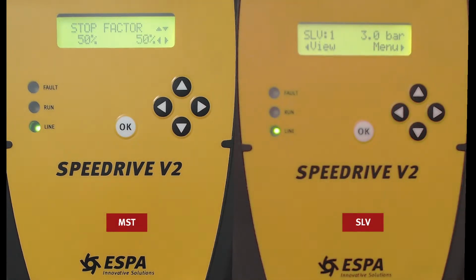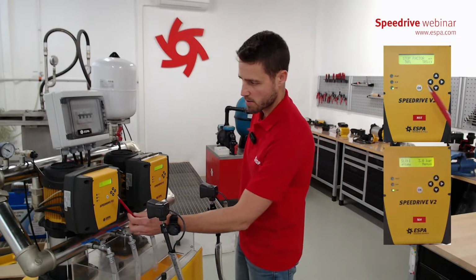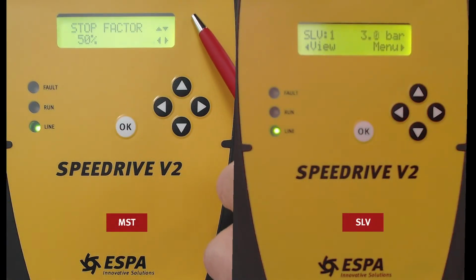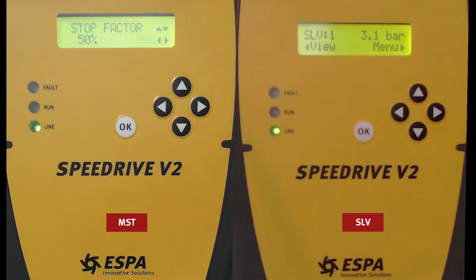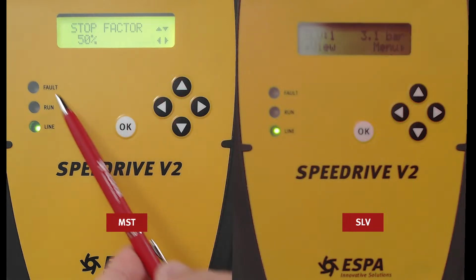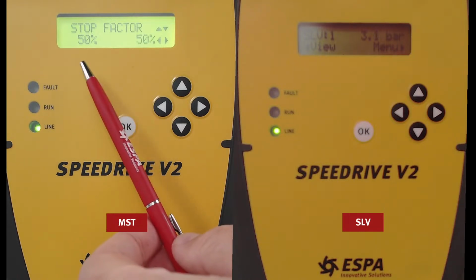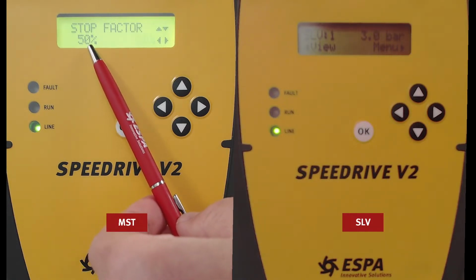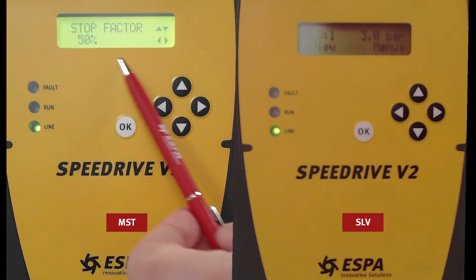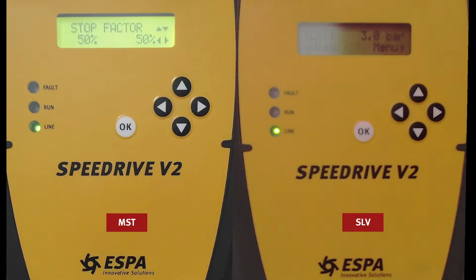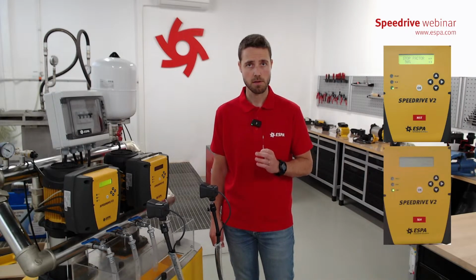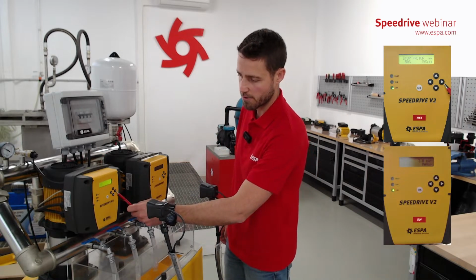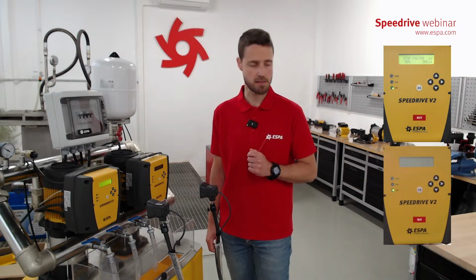And the stop factor. What is the stop factor? 50%. This is the factor where the pump, in case of dry running, will stop. For example, imagine you have no pressure because the installation is empty, we are running dry, the intensity will go down, and when we reach the 50%, the pump will stop. This is very important to protect the pump. In case the pump is not stopping, we have to increase this value or check the maximum intensity of the pump.